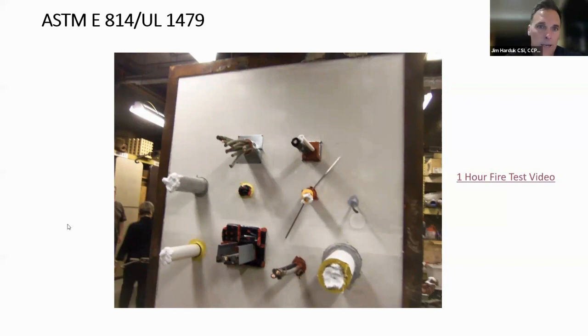This is not uncommon when the Firestop manufacturers go to run one of these tests. First they construct the floor or wall assembly, whatever condition they're testing. And then typically they'll test multiple Firestop products in the assembly at one time. These tests are pretty expensive, anywhere from $10,000 to $30,000 a test. And if you fail the test, you don't get your money back. So when the manufacturers are doing these tests, they want to be pretty certain that whatever they're going to test is going to work for that application. So if you would right now, if you could start the video.